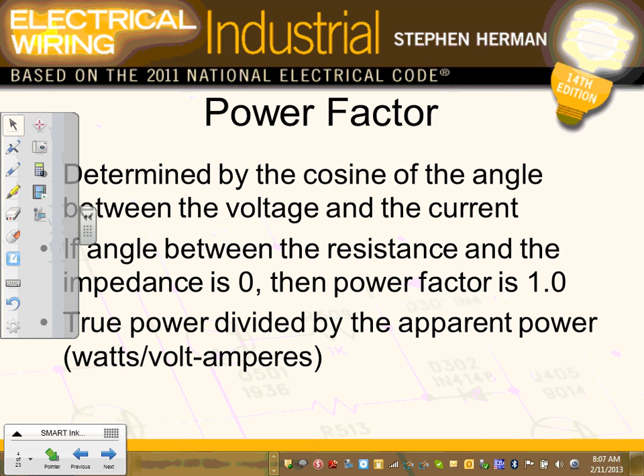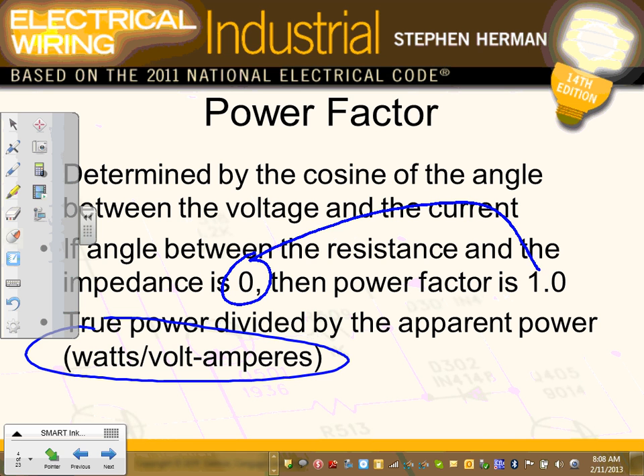Okay, so when you define your power factor, it's always the watt over the volt amp. Your watt over the volt amp. Your power factor can go from 0, where you would hope you would never be, to 1. If you have a 1, or 100% power factor, you have a purely resistive load. 99% of the time, Andrew, your power factor is in the 90s. If you can maintain your power factor between 90 and 97 in your plant, you're good. You don't want to go to 100 because if you go to 100 when you turn certain loads off, what's going to happen?